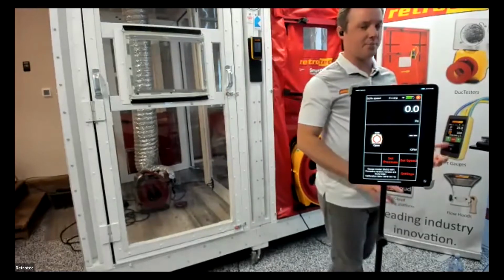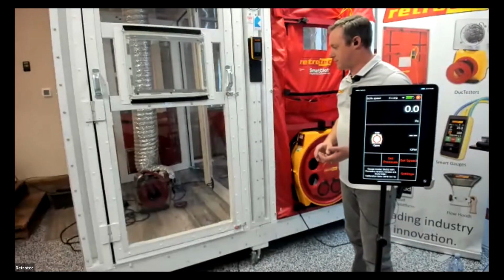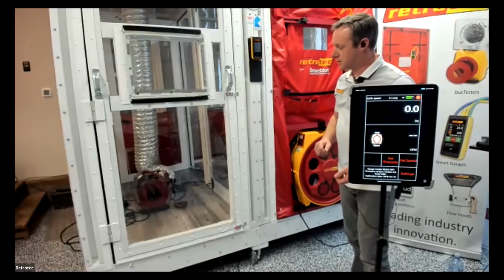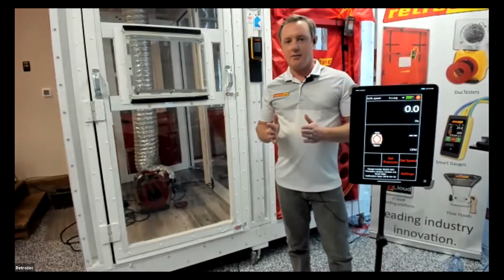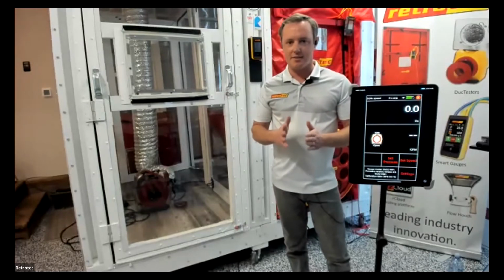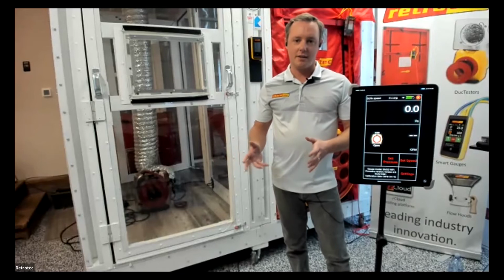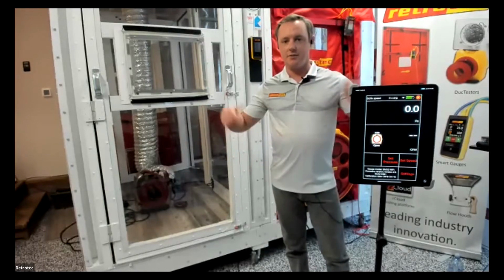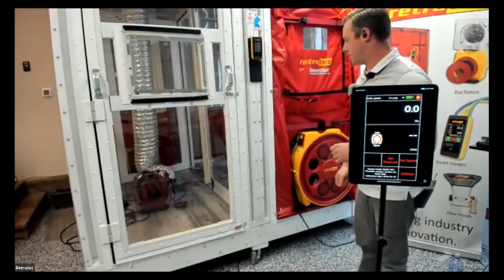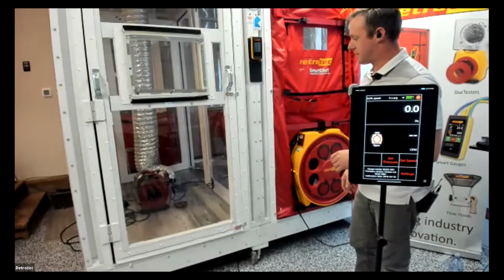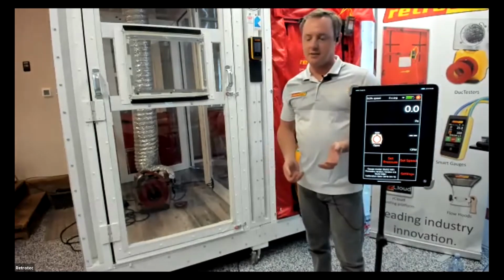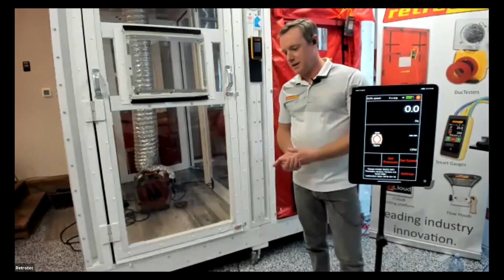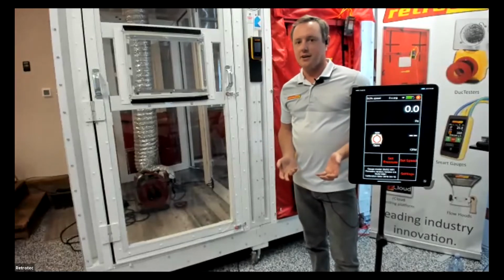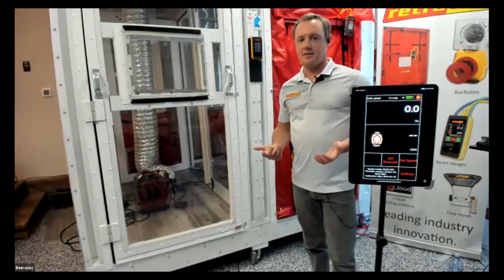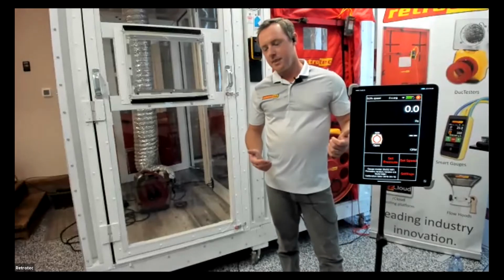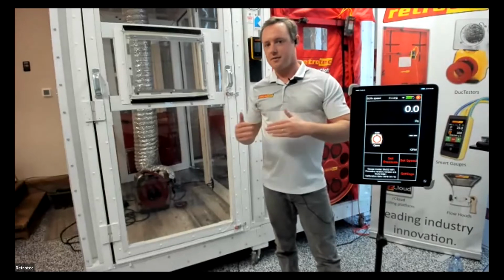What we're doing here is called pressure matching. And by doing this, by seeking zero, we're just neutralizing the pressure between that duct system and the interior space. That way, the only reading that's left over is any duct leakage from the outside of the building. So by neutralizing that space, it's going to cancel out any interior leakage. If you're familiar with blower door testing, like guarded testing for apartments or townhouses, it's a similar thing. In that case, you're neutralizing the pressure between a common wall, but here we're just neutralizing pressure between the duct system and the interior space.